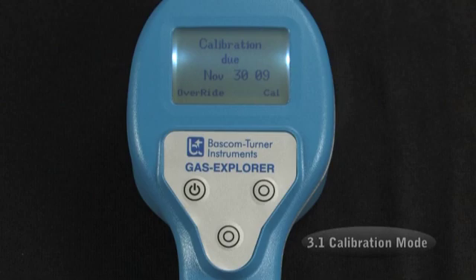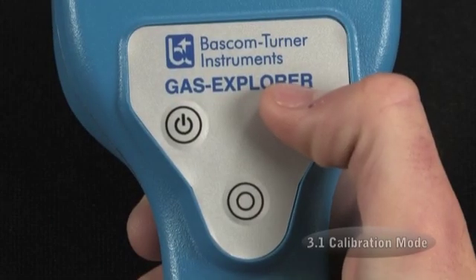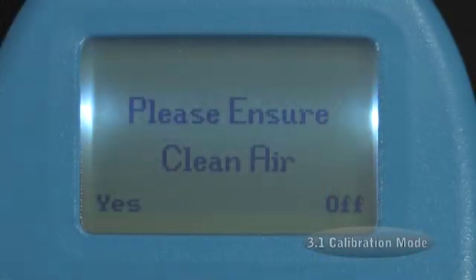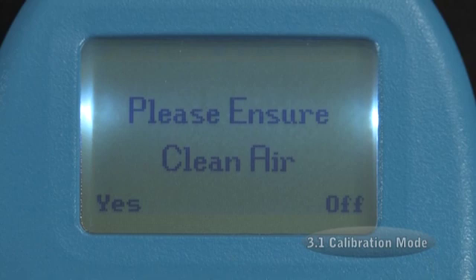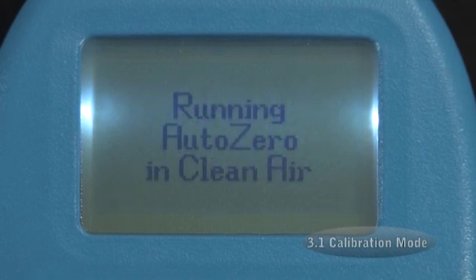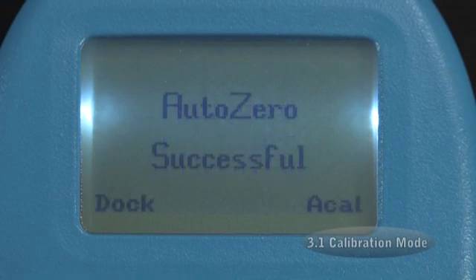If it is overdue, then the Calibration Overdue screen will appear and stay visible until either you override it by pressing the left button or initiate a calibration by pressing the right button. After pressing the CAL button, the Explorer will display the message, "Please ensure clean air." Press the left button under the word Yes to initiate the auto zero needed prior to calibration. The Explorer will display Running Auto Zero in Clean Air for approximately 25 seconds, and then display the Auto Zero Successful message. At this point, you see the words Dock and ACAL at the bottom of the screen.